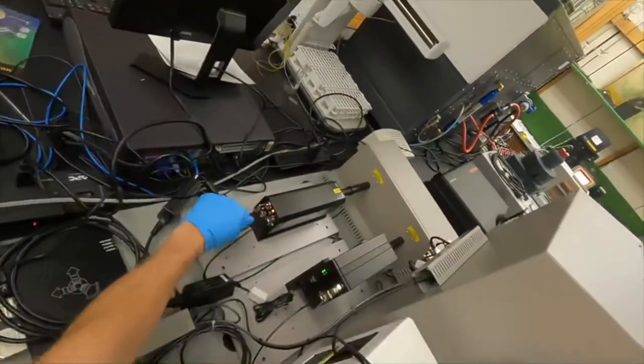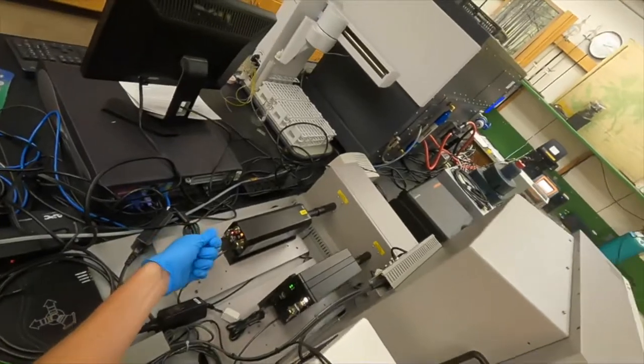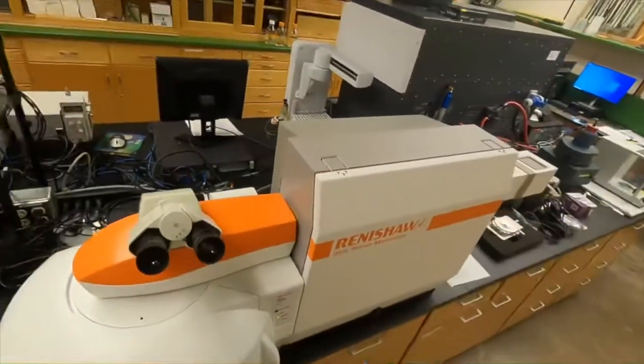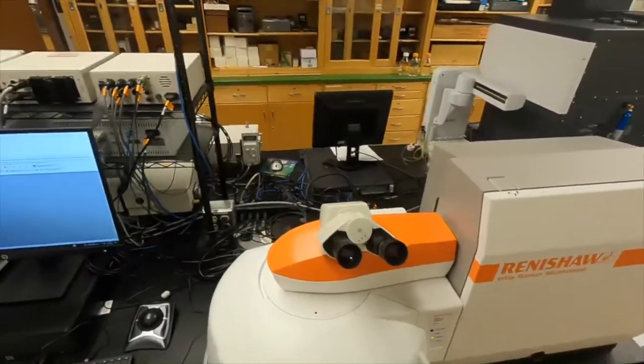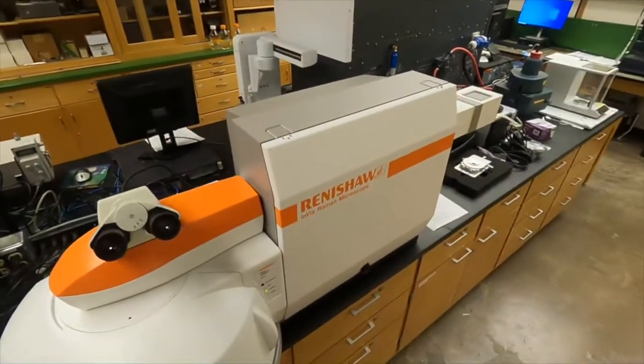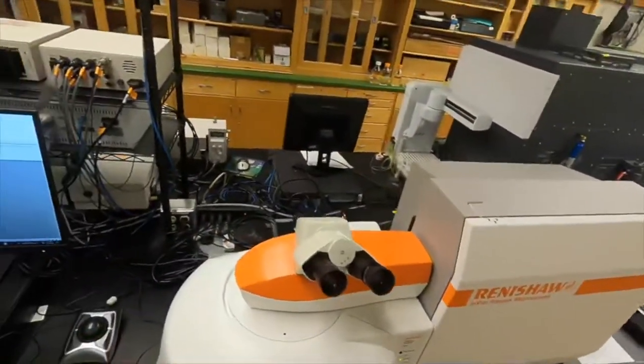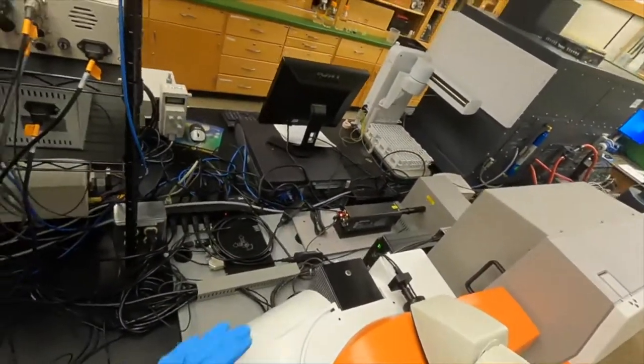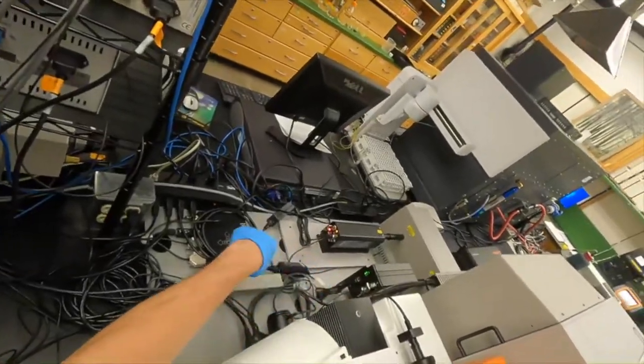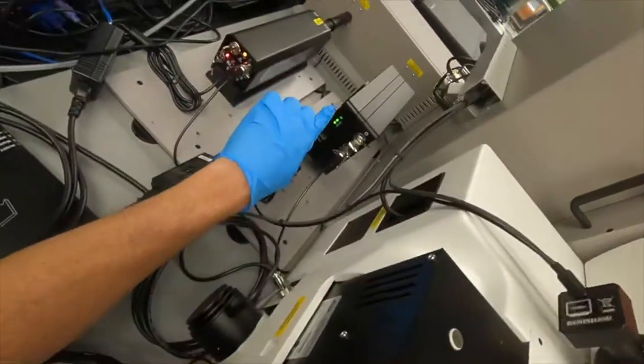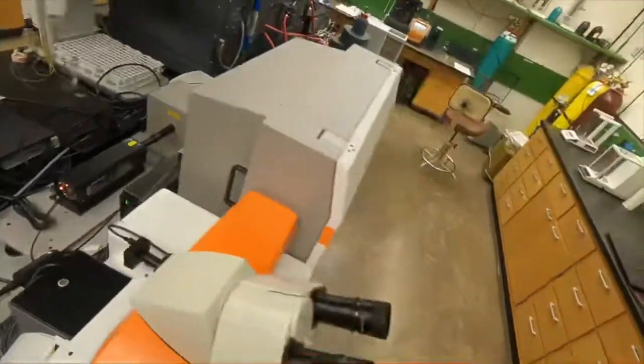So you can just turn it off using the key and then turn it back on. Usually I open and close the door a few times to try to reset the failsafe on there. You can also play with turning the microscope on and off to reset that. But yeah, these are good to go because we've got the top light and bottom left light. And on this laser, both the lights are on, so we're good to go.